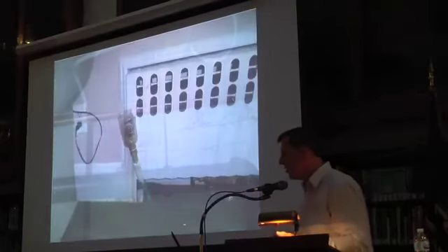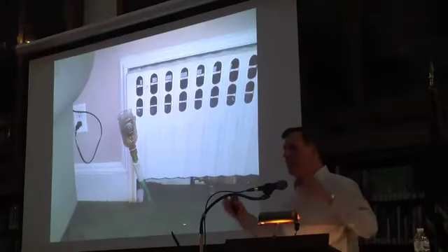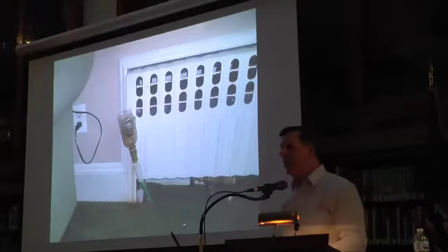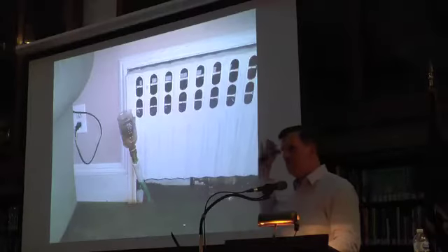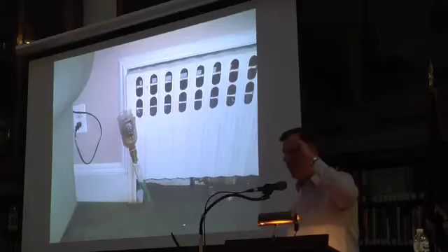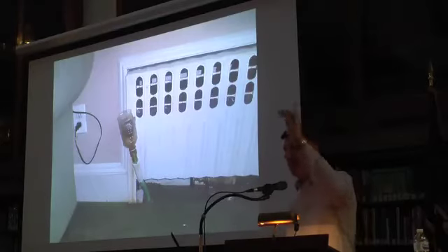But sometimes the vents squirt, and then the knuckleheads show up, and they're going to solve these problems. So this was one that happened out on Long Island. The people added an extension to the back of the house. Out over the back door, they put a separate room, and it's an old steam heated house. So they ran a steam main off the main that was feeding the rest of the house horizontally into the crawl space, dead level, because this was a guy that felt that pipes really had to be level rather than pitched. He wasn't thinking like water wants to flow downhill, right? So dead level pipe going out and then up into this radiator that was on the far side.